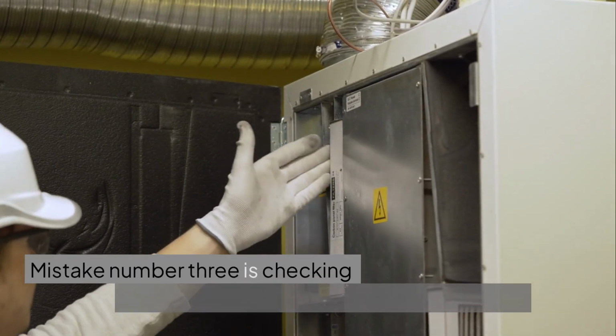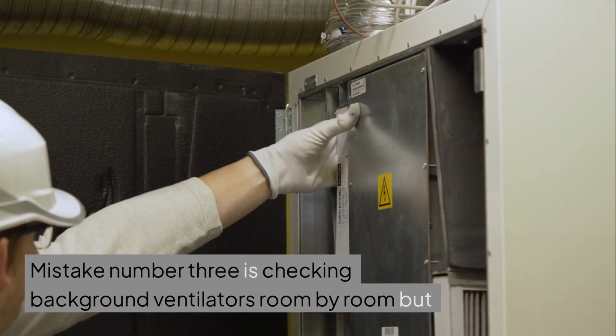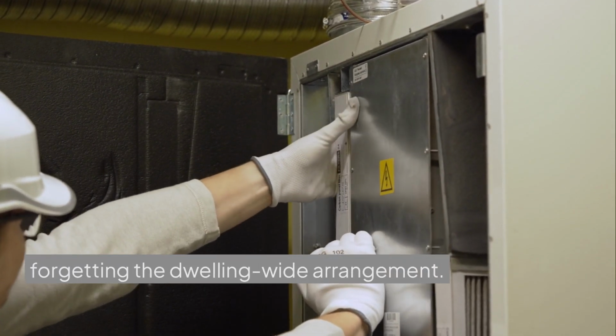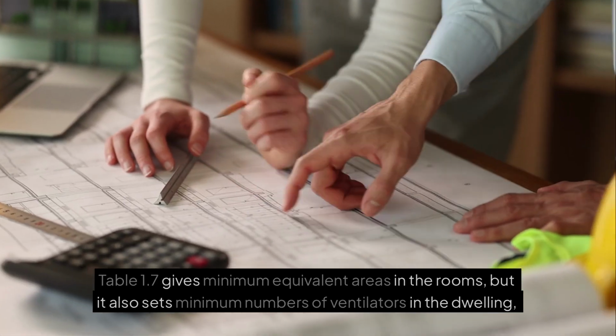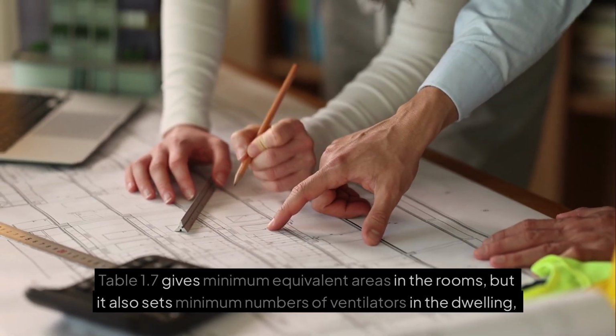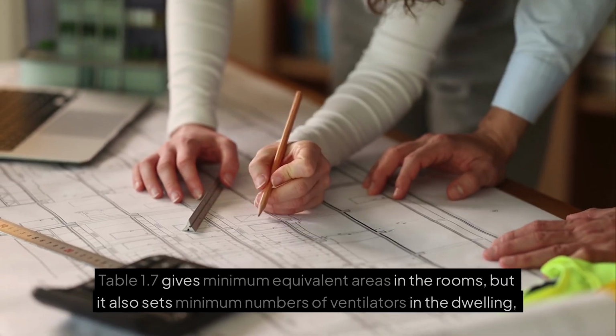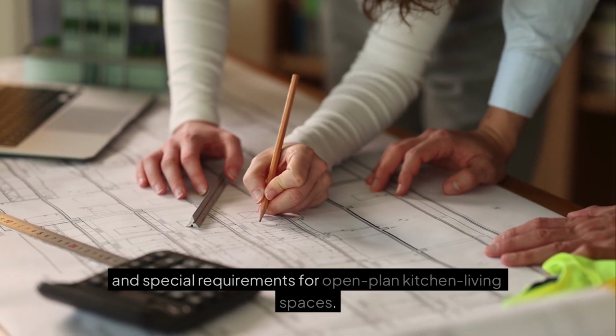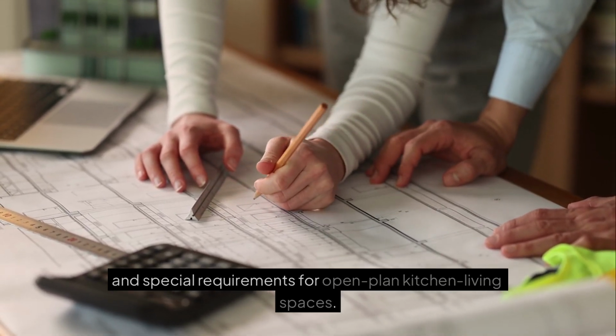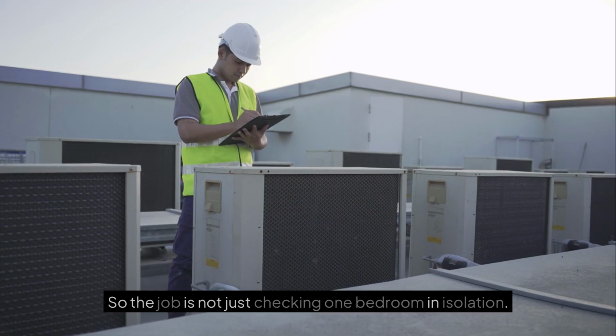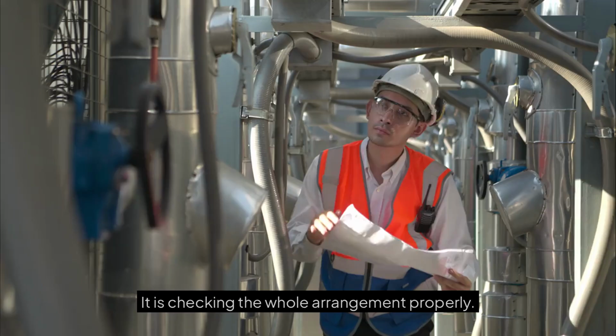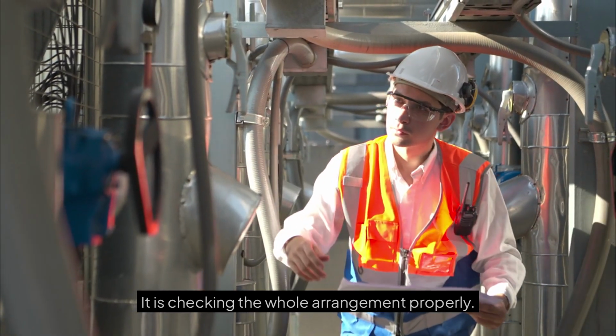Mistake number 3 is checking background ventilators room by room but forgetting the dwelling-wide arrangement. Table 1.7 gives minimum equivalent areas in the rooms, but it also sets minimum numbers of ventilators in the dwelling and special requirements for open-plan kitchen living spaces. So the job is not just checking one bedroom in isolation. It is checking the whole arrangement properly.